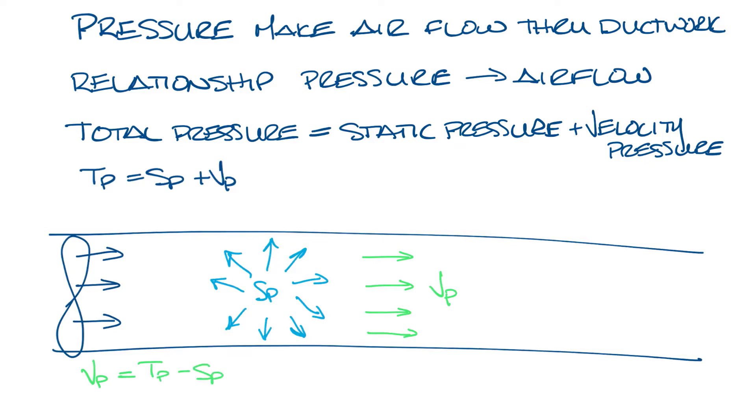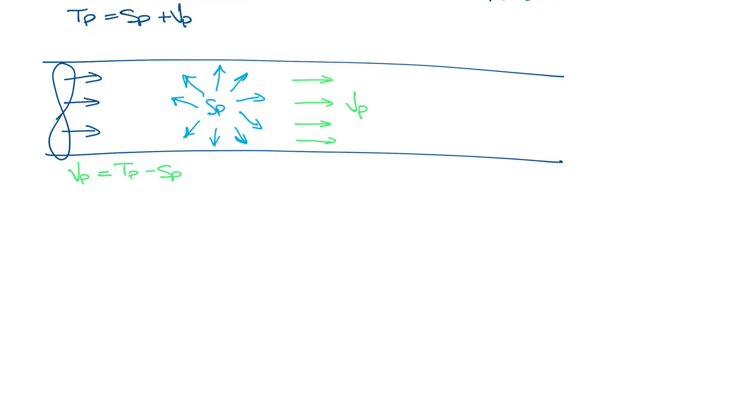So let's make some room and look at how we measure pressure in our ductwork. A pitot tube is used to measure pressure. A pitot tube is a tube with a hole pointing in the direction of air flow that measures total pressure, and a hole pointing perpendicular to air flow which measures static pressure. It's basically a tube within a tube.